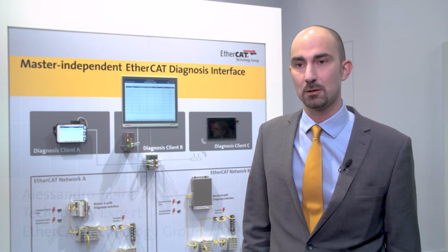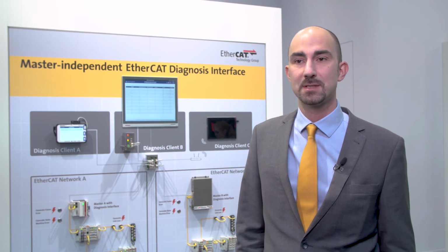The diagnostic capabilities are one of the most important features in determining the success of a fieldbus technology, and EtherCAT provides outstanding diagnostic information both at hardware and software level, enabling not only to detect errors, yet also to precisely locate them. The ETG document 1510 enhances the EtherCAT master classes specification, defining a master-independent profile to provide information to client applications like diagnostic tools or HMIs.